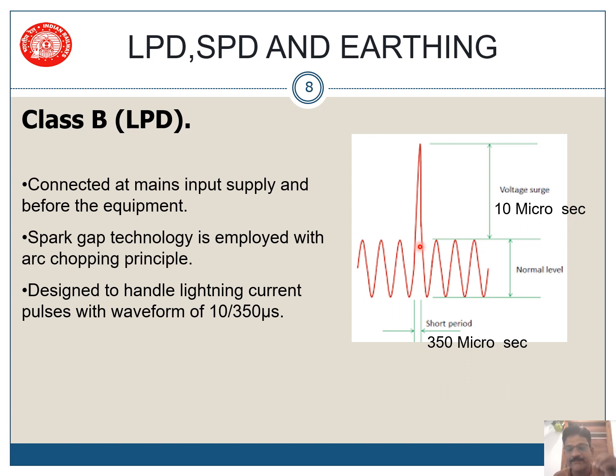200k amps of current, 2 लाख एम्पियर करंट का जनरेशन हुआ है बिकॉज ऑफ लाइटनिंग, और वो 10 माइक्रोसेकंड में इंक्रीज हुआ है from 230 volts, it has increased to some 50,000 volts within 10 microseconds, and it has stayed there for a time period of 350 microseconds. So what is the meaning? Normal 230 volts 10 amps has suddenly increased to abnormal voltage and abnormal current within 10 microseconds and stayed there for 350 microseconds. 350 microseconds तक वो वोल्ट करंट और हाई वोल्टेज और करंट था. अगर वैसा है तो भी आपका लाइटनिंग प्रोटेक्शन डिवाइस जो है क्लास बी, वो आपके इक्विपमेंट को प्रोटेक्ट करेगा. ना अगर वो लाइटनिंग बहुत ज्यादा देर से है, यानी 350 माइक्रोसेकंड से ज्यादा है, लेट अस से इट इज फॉर 1 सेकंड, तो ये सिस्टम प्रोटेक्ट नहीं करेगा.